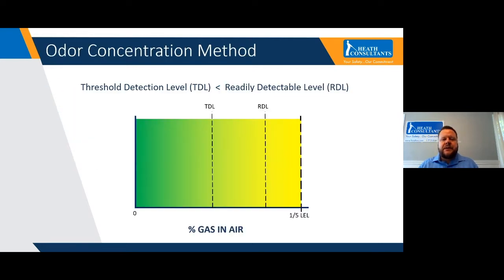So the odor concentration method is where you use the piece of equipment that has ambient air flowing through it, and you use a valve to start introducing gas from your gas system into the instrument. So once your gas and air mixture starts to mix, you use your nose to begin to smell that ambient air. Now, at the moment when you start to smell that ambient air change, you maybe don't know that it's natural gas. Maybe it just smells slightly different. You know that there's something different in the air. That's what we call the threshold detection level. Now, at that point, to continue the test, you would continue to introduce gas into the instrument and continue to smell. And at the point when you know that the smell that you're smelling is absolutely natural gas, that you're ready to take action, to call your operator or call your first responder, we call that readily detectable. That's where somebody smells it and they say, aha, that is natural gas. No question about it.